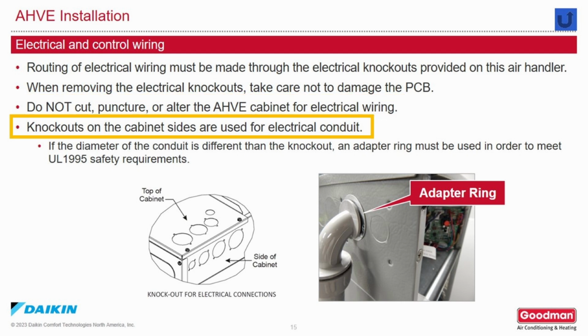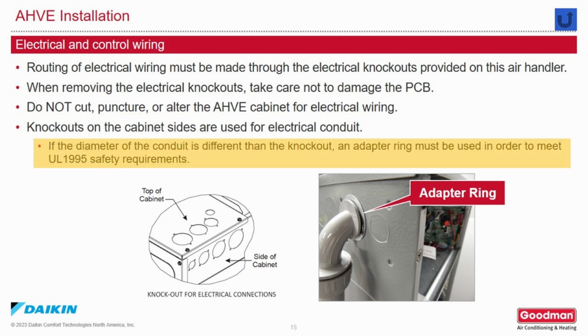Knockouts on the cabinet sides are used for electrical conduit. If the diameter of the conduit is different than the knockout, an adapter ring must be used in order to meet UL 1995 safety standards.